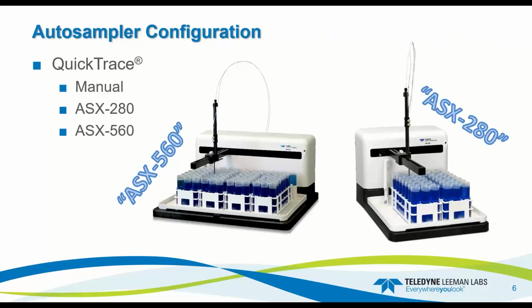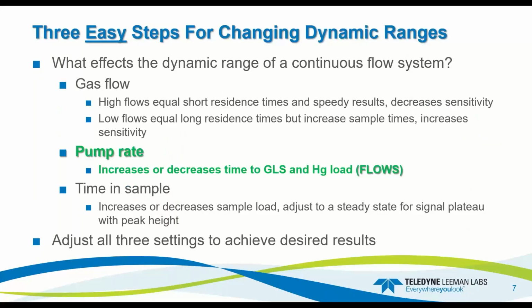So the autosampler configuration that can be packaged with the system is either the 560 or the 280. The 560 is a 4-rack system and the 280 is a 2-rack system. You also have the option to run without an autosampler if you only have 1 or 2 samples a week. Calibrate using the probe. You manually move it to and from the rinse station and to and from the standards and or samples.